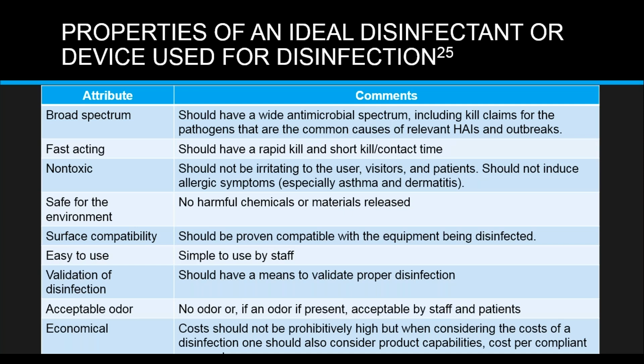For chemicals, you need to look at time and concentration, for instance. No odor. If there's an odor present, it's acceptable. And then ideally, they should be economic. That is both compared to other methods and certainly economic compared to the outcome we're trying to prevent. So we're going to turn to two devices that are used for high-level disinfection of endocavity probes.